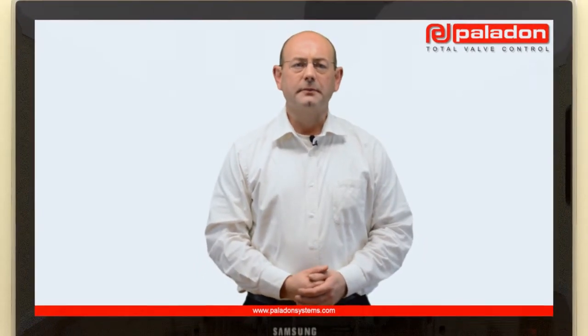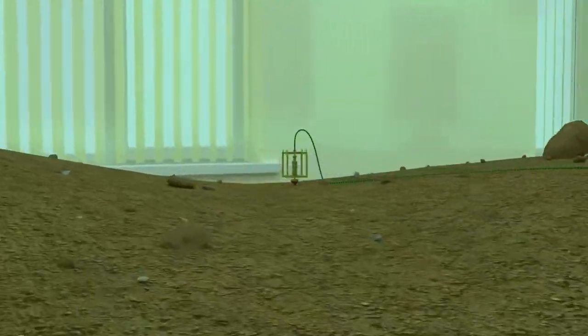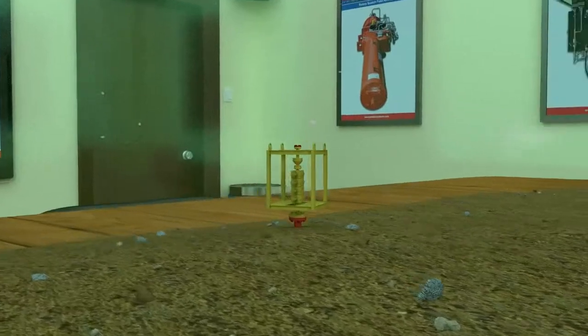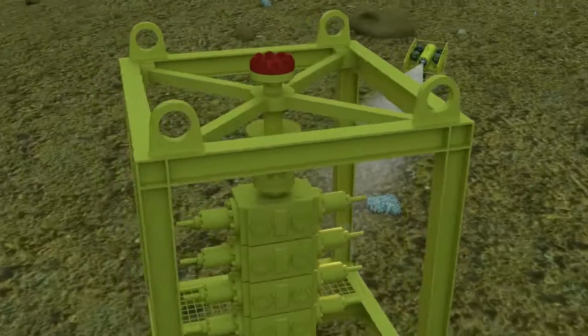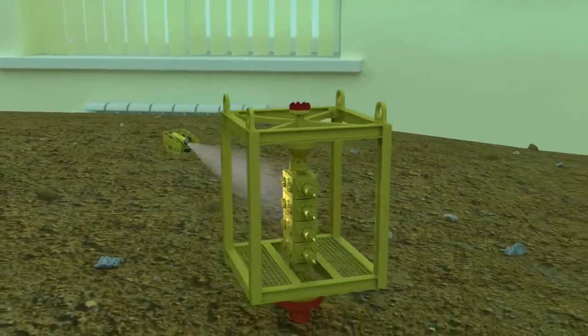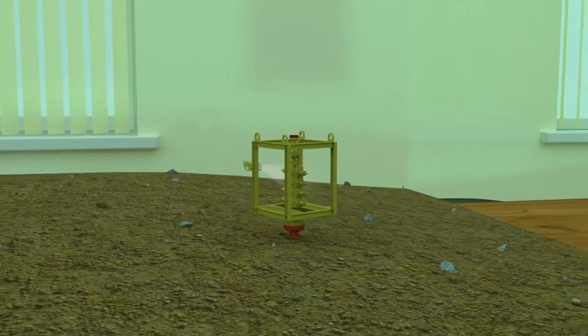Let's have a look at a common application for HIPPS. In this example, we have an oil rig which has been producing from three wells for many years. These wells have been producing oil at stable pressure rates of less than 100 bar and accordingly all downstream infrastructure has been designed to operate at the maximum pressure of 100 bar. A fourth well was drilled several years ago; however, it was found to produce oil at fluctuating pressures which could occasionally spike to as high as 200 bar. As the existing infrastructure was only rated to 100 bar, it was deemed uneconomic at the time to upgrade the pressure rating of the infrastructure and so the well was never brought online.